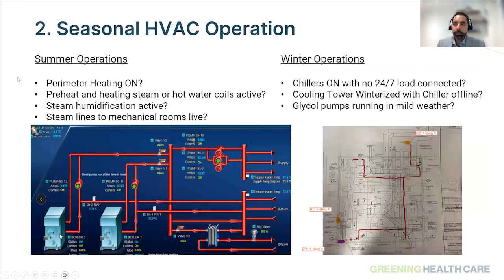The second area where there could be immediate improvements is around seasonal HVAC operations. One of the key pieces of information coming back from some of these facilities is around perimeter heating being on in summer operations. We looked at a lot of these facilities, and there's no good reason for the perimeter heating system to be on in the summertime. And whenever it's on, along with the preheat heating coil being active, we notice that generally that load ends up in a chiller plant. And we'll show you an example of that.